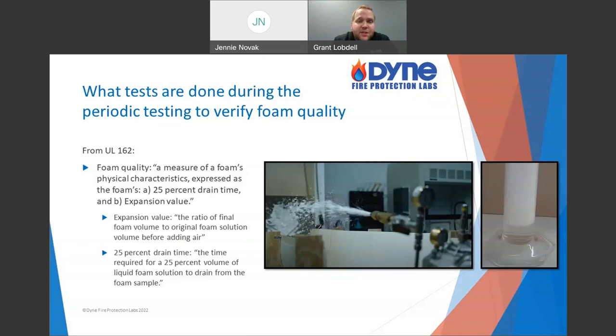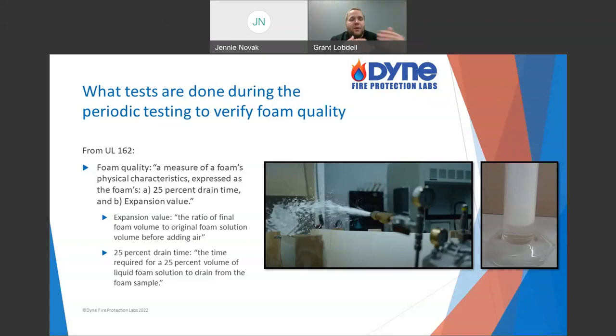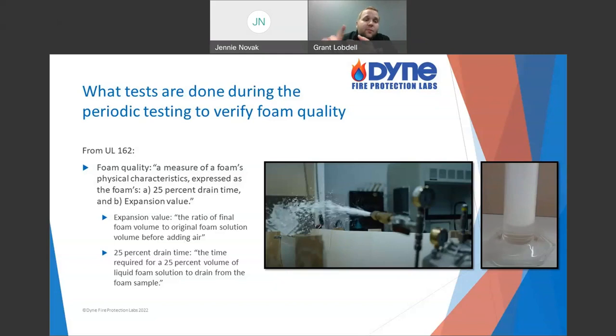I'll point you to UL 162, which is an example of a listing standard. When you have a foam product and it's going to be listed — UL is just one example — they're going to use UL 162 as the basis for listing this product. In that document, they define foam quality as a measure of foam characteristics expressed as 25% drain time and expansion value. So drain time and expansion value are really the main things we're talking about with foam quality, though there are other tests as well.